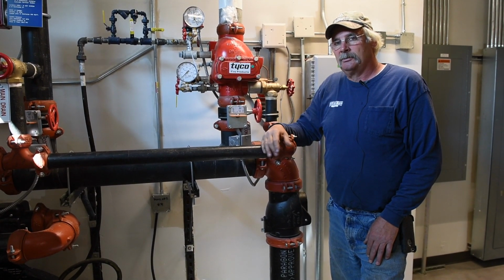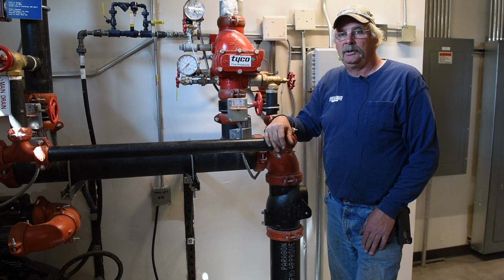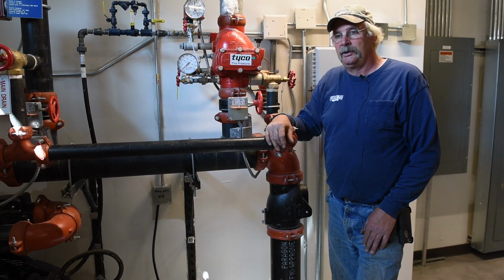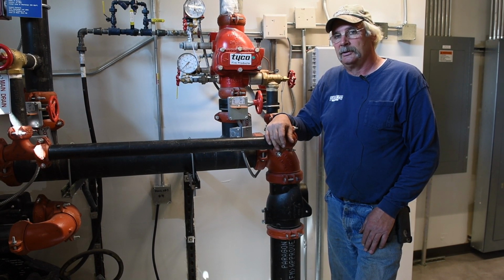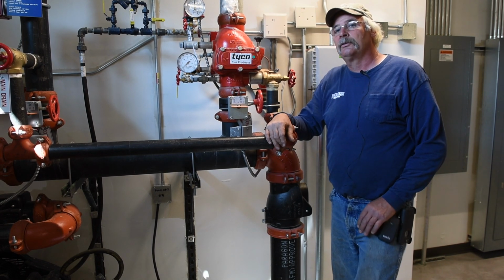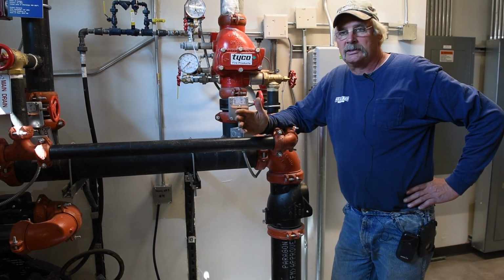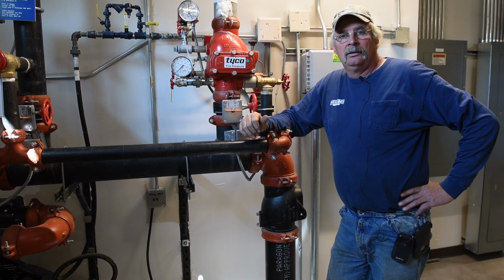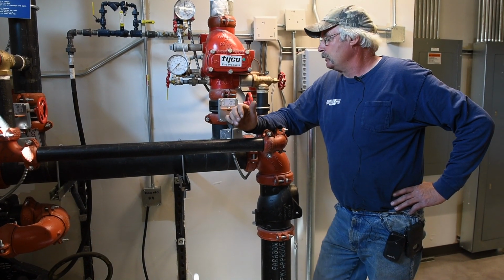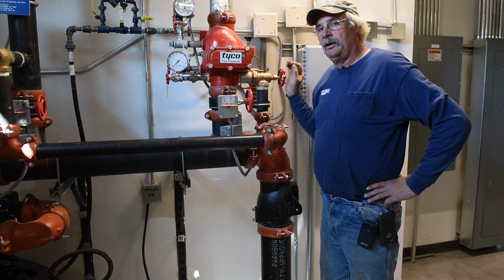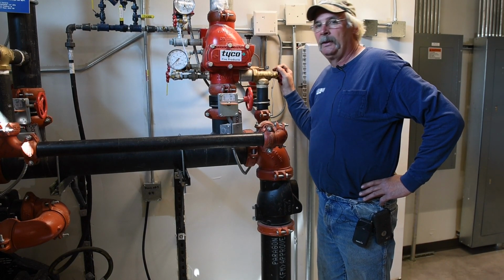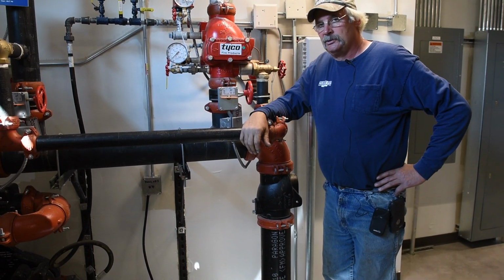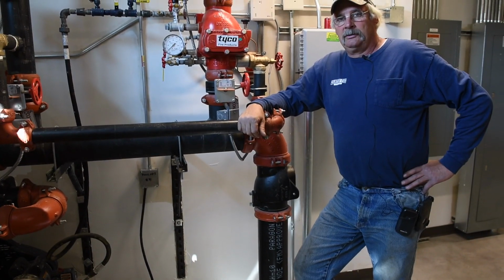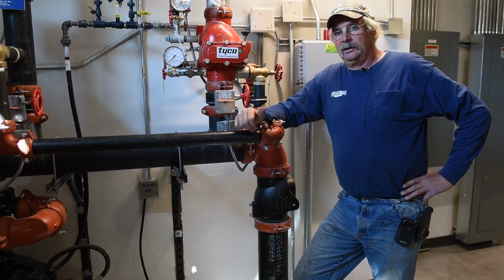On this dry system, because the facility goes up and down, we have a low point drain, which is just inside the main entrance door. After a trip on a dry system, due to loss of heat, loss of power, whatever, you have to make sure you shut the control valve off, thoroughly drain the system, and open the inspector's test, which is just inside the west entrance door of the main facility.